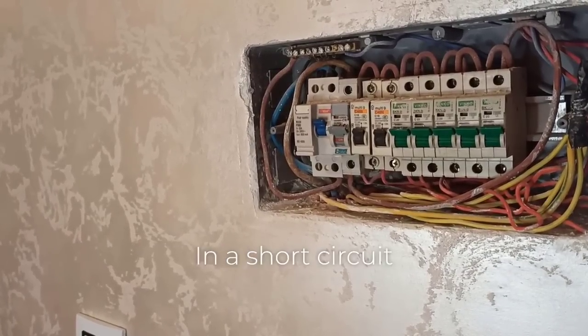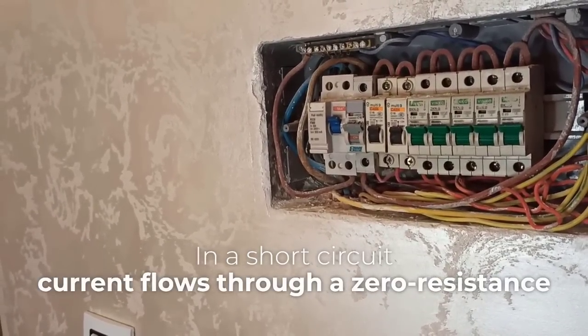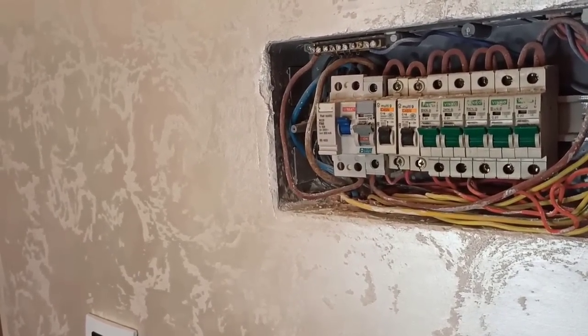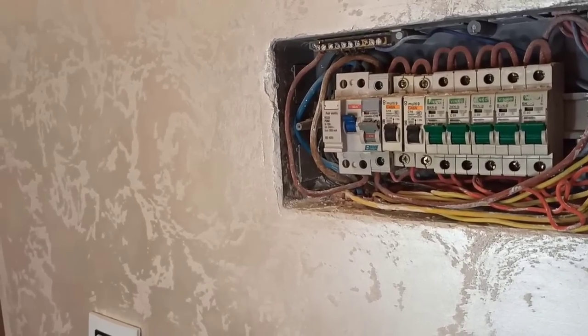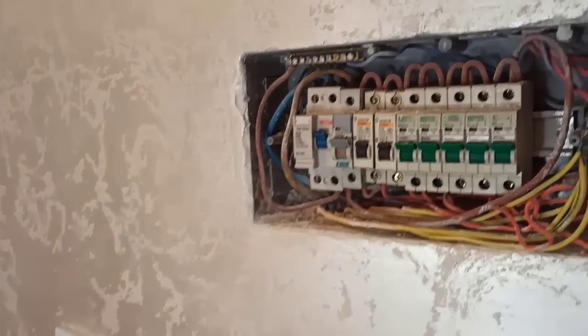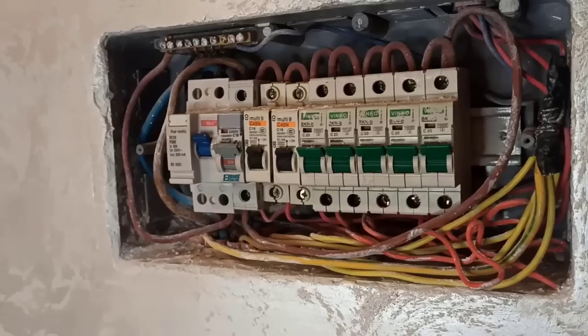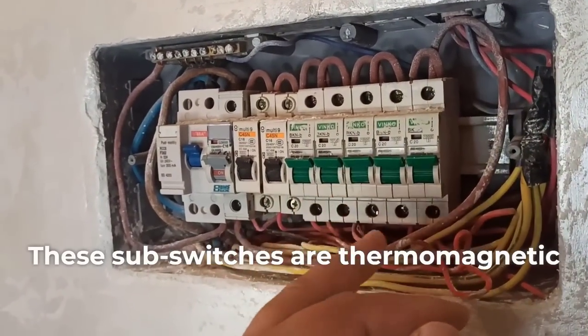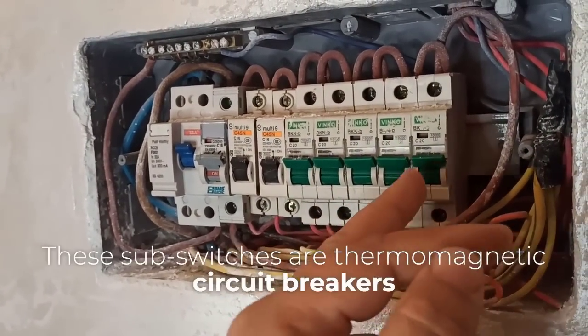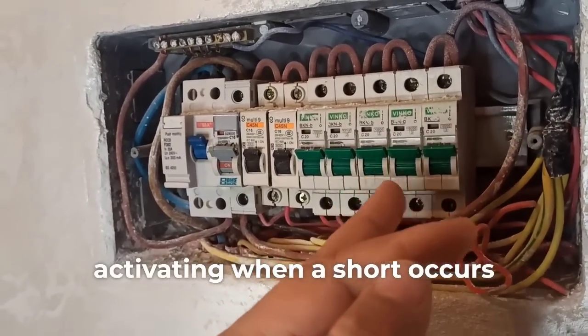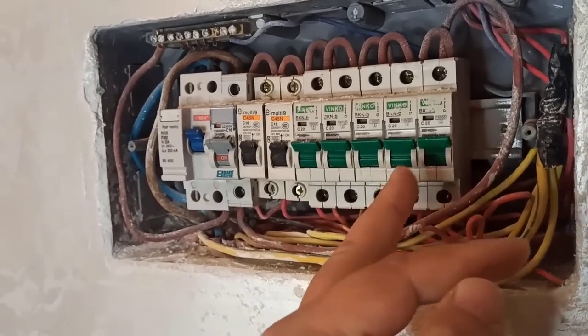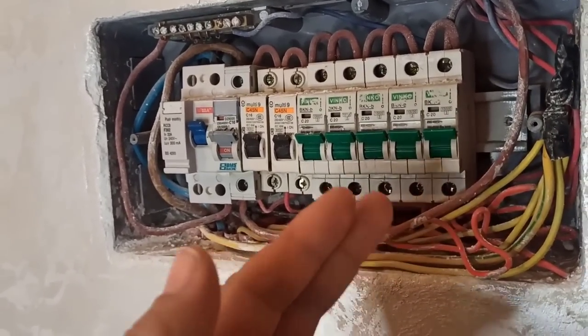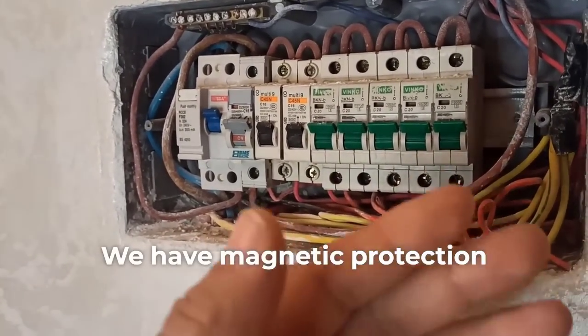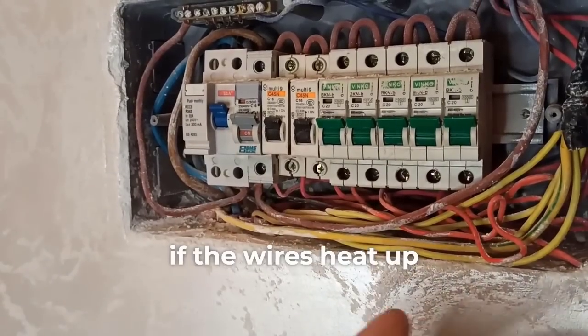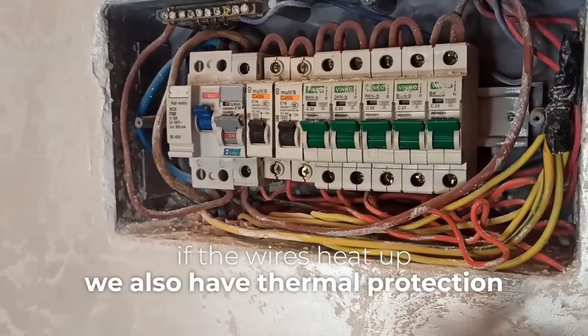In a short circuit, current flows through a zero resistance path. These sub-switches are thermomagnetic circuit breakers, activating when a short occurs. We have magnetic protection, and in case of overload, if the wires heat up, we also have thermal protection.